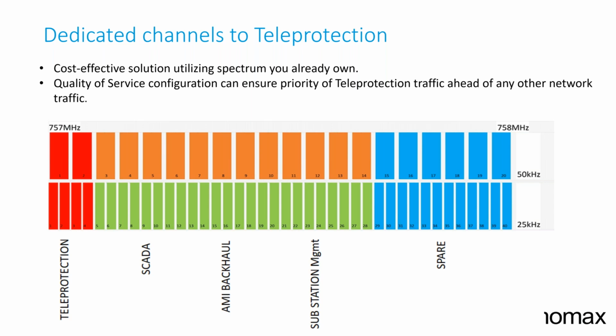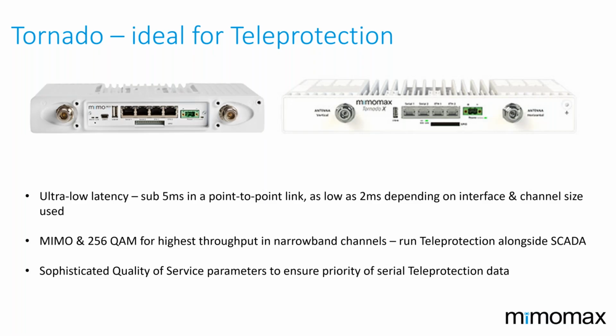In terms of the radios themselves, the Tornado radio, as I mentioned earlier, is self-contained. Duplexes are all built in. We have Ethernet and serial interfaces natively on the product. It's got a very, very low latency for point-to-point, as we discussed, as low as 2 milliseconds, depending on interfacing and channelization. It supports MIMO. QAM256 is our highest throughput, but that also equates to the lowest fade margin. So if we could hit a 256 channel, that would be great, but typically we see these applications in around 16 QAM or 64 QAM. And even with that, there's still enough bandwidth to run alongside the SCADA requirements.